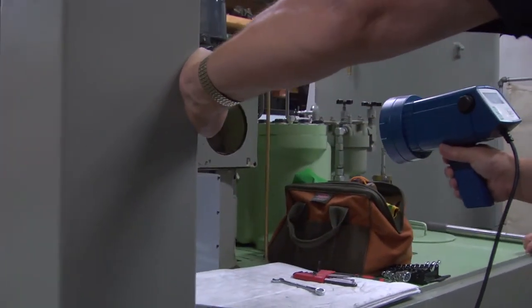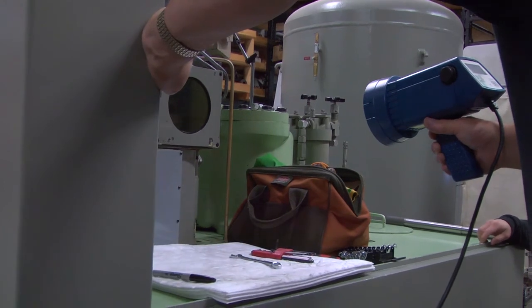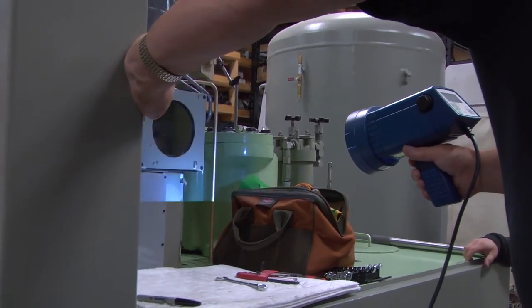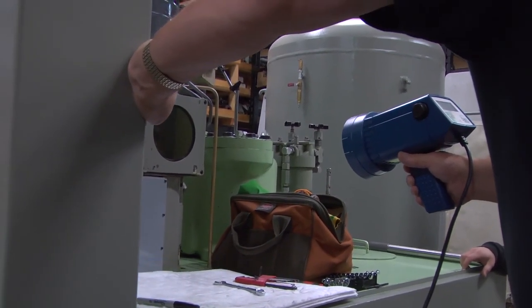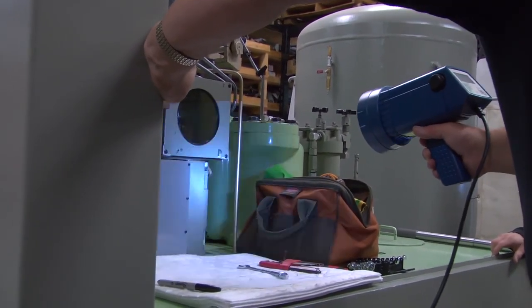This is when you'll really find it. If you've got a PMG problem and it's low, and you wonder if that's causing your hunt, you grab one of these and put it on there. You'll see this in this position. It'll sit there like this and go, and you'll be able to look right over there, and those weights will be moving at the same time as this is flopping around.